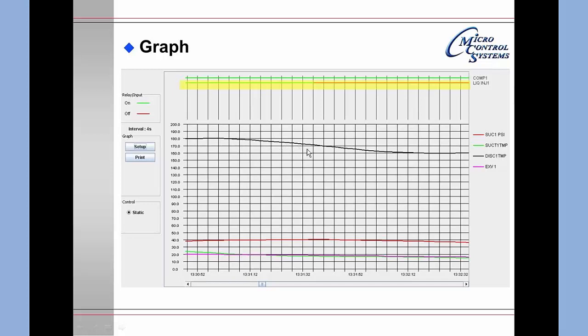Liquid injection is on and it drives us down and we shut down at about 170 degrees discharge temperature. However, if you continue across you will see that even after we shut it off it continued to drive the discharge temperature down to about 160 degrees. So we had a drift of over 10 degrees.